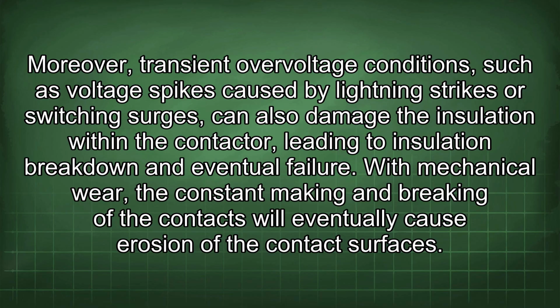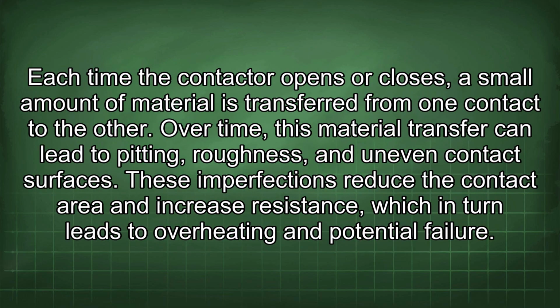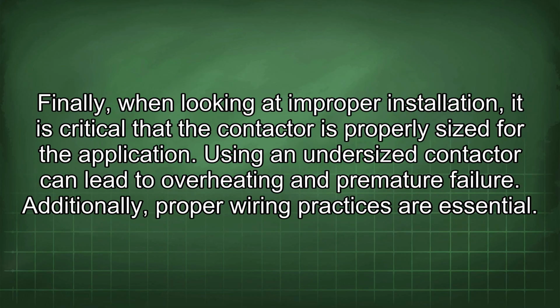With mechanical wear, the constant making and breaking of the contacts will eventually cause erosion of the contact surfaces. Each time the contactor opens or closes, a small amount of material is transferred from one contact to the other. Over time, this material transfer can lead to pitting, roughness, and uneven contact surfaces. These imperfections reduce the contact area and increase resistance, which in turn leads to overheating and potential failure. Finally, when looking at improper installation, it is critical that the contactor is properly sized for the application.